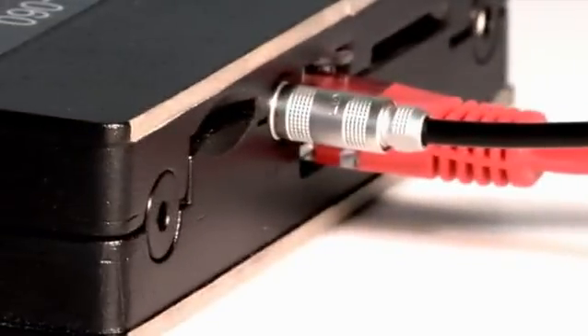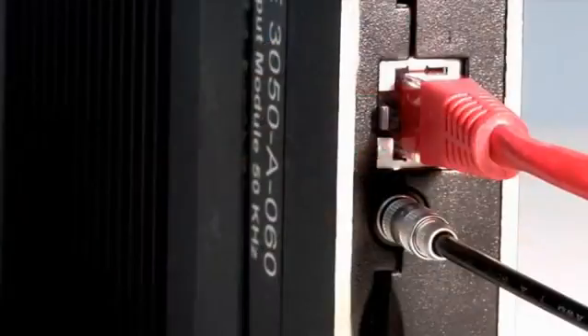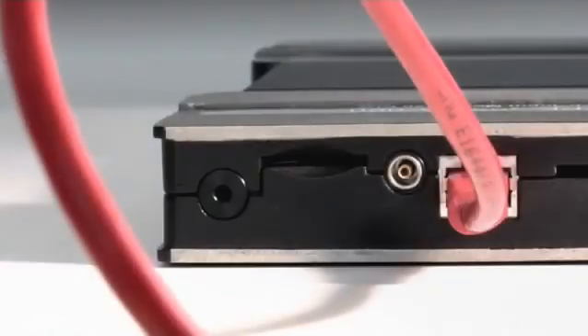Each module can be powered by 10 to 32 volts DC, allowing the whole system to be operated from, for example, a car battery. LAN-XI can also run on PoE, that is, wired Ethernet LAN technology.